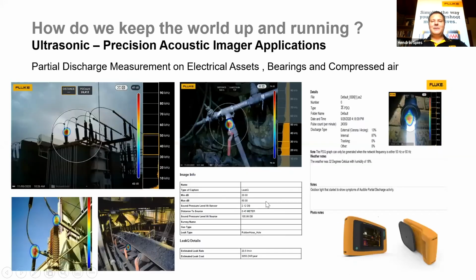So let's deep dive a little bit. So let's look at ultrasonic. So on the ultrasonic side, we're going to refer back to the precision acoustic imager. And what's nice about this technology, you can use it for electrical, mechanical, and compressed air and gas applications. So let's deep dive a little bit. If you have a look here on this photo, this is a photo I personally took in South Africa. This is a transformer, 132 kV transformer system, substation, and we picked up some problem here on this connection.